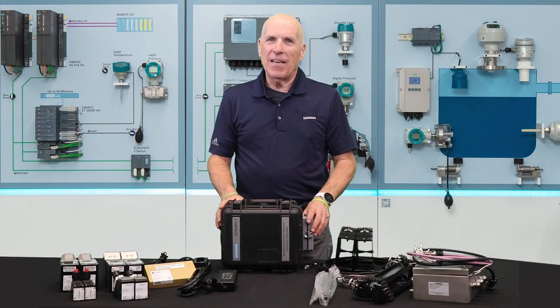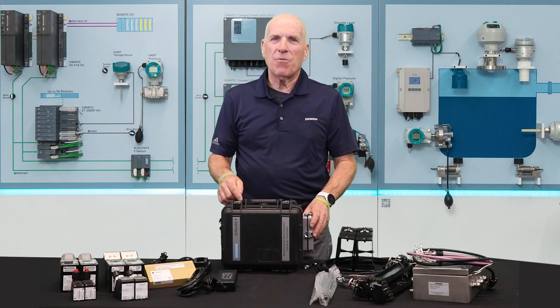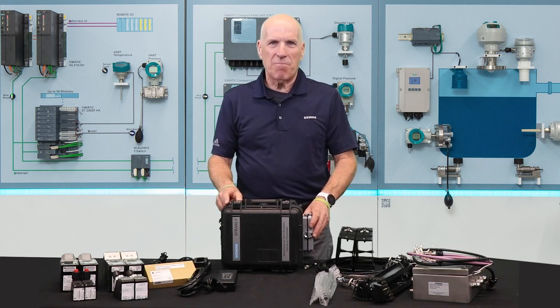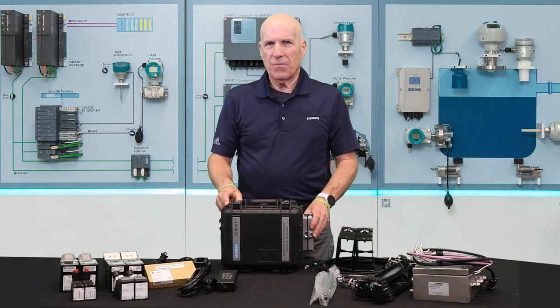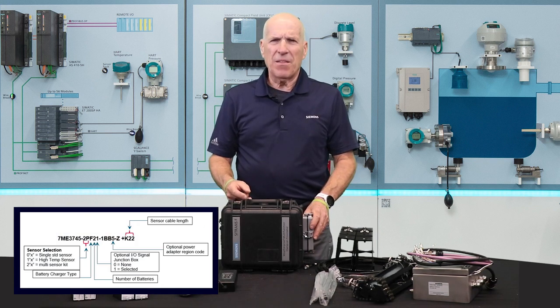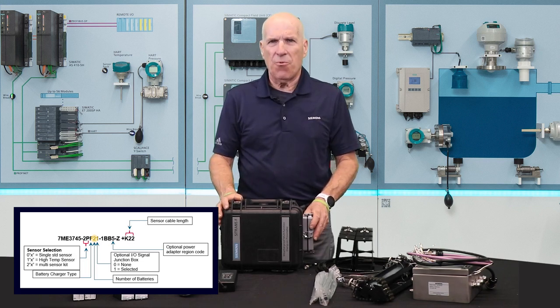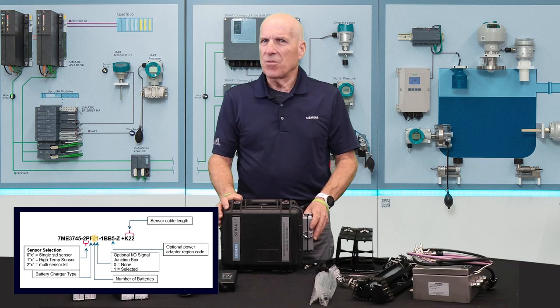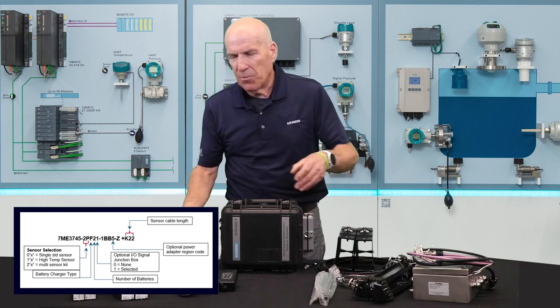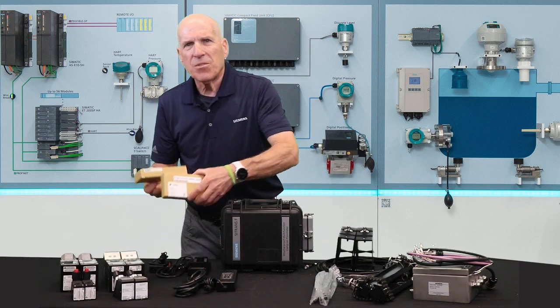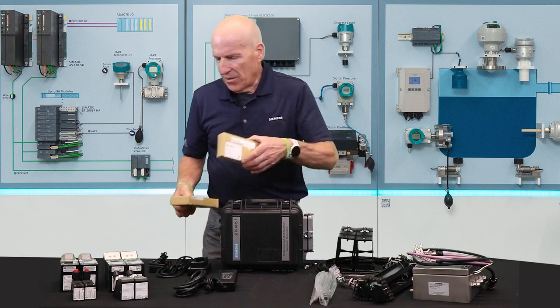Since the FS290 system is primarily powered from its rechargeable lithium battery, there is an option to purchase up to 3 of them. The number of the batteries supplied with the order is indicated by the number in position 11 of the system part number as a 0 through 3. This meter indicates a 2, so 2 batteries were supplied. This enables continuous use while the second battery is charging.